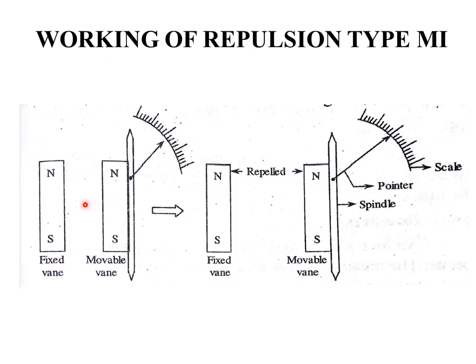Initially there is no current flow through the coil, so the fixed vane and the movable vane remain in their static position and the pointer shows zero deflection. When current flows through the coil, it creates a magnetic field, causing both the fixed vane and the movable vane to be polarized with the same polarity — both having their north pole at the top and south pole at the bottom. Like poles repel each other, and according to this repulsion and the current flow, the pointer shows deflection.